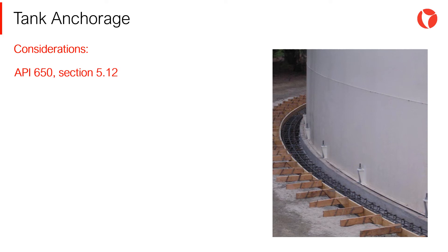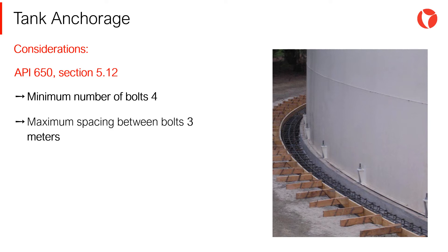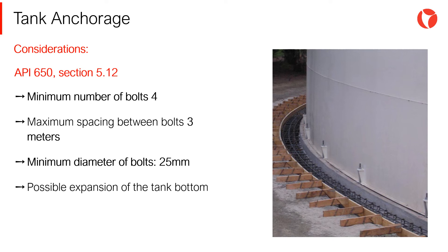Some of the most important requirements when designing anchor bolts are: the minimum number of bolts should be 4, maximum spacing between bolts is 3 meters, the minimum bolt size is 25 millimeters, and anchor bolts must be designed to absorb possible expansion of the tank bottom as a result of high operation temperatures, usually above 93 degrees.